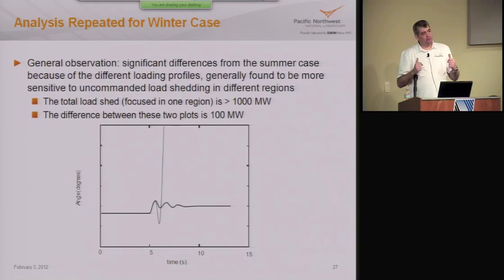Well, when you're shedding load, we found that it was actually more beneficial to shed load under those really stressed conditions, because you're relieving stress on the transmission side, particularly if you shed load in a pocket where it's importing power. The most sensitivity that we had in the previous plots was in an area that was exporting power. If you're in an area that's exporting power and you shed load, you generally put a disproportionate increase on the transmission infrastructure, and that increases stress, and that's what causes these problems. So my bottom line is that studying peak loading for summer isn't necessarily going to give you the most sensitive results.